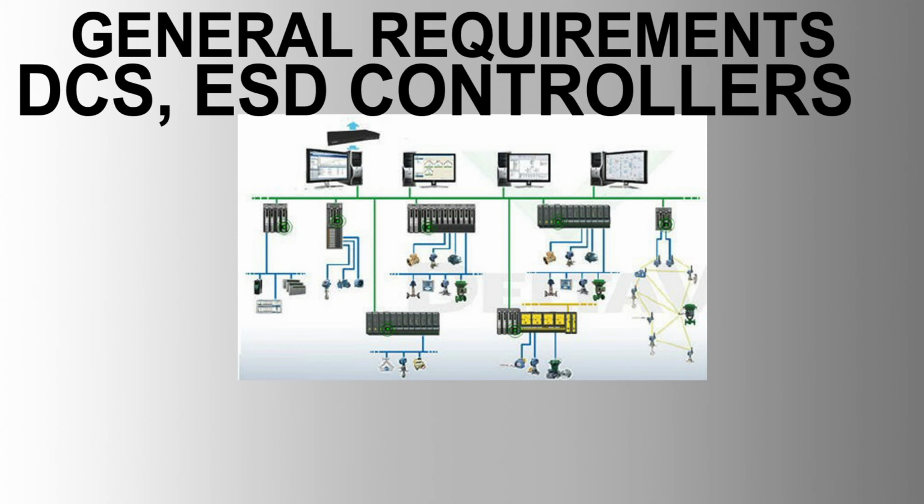Cabinets must meet IP54 certification as a minimum and include cooling fans and dust filters for proper ventilation. Cabinets should have dual redundant power supplies and cooling fans designed for redundancy to ensure continuous operation even in case of component failure. Tags for cabinets, racks, JBs, distribution boards, and terminal blocks should be engraved and fixed permanently.